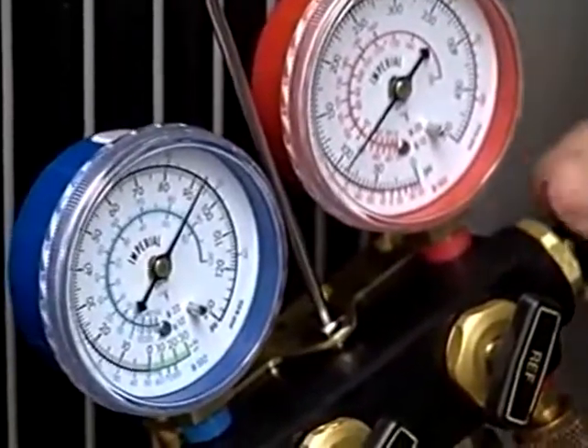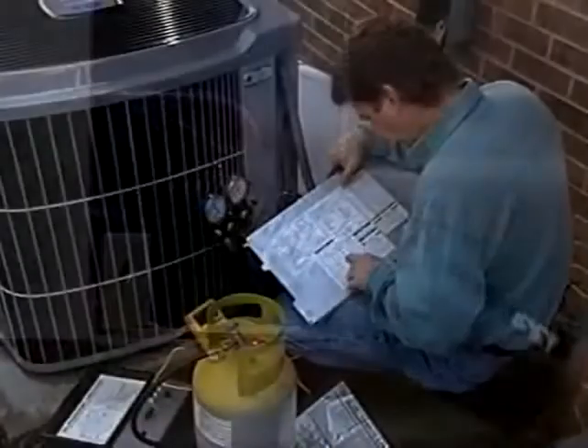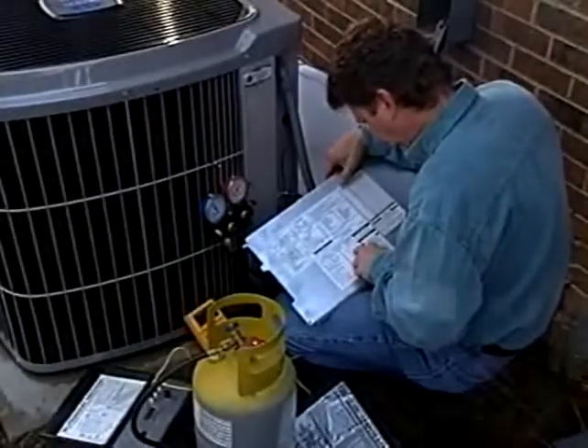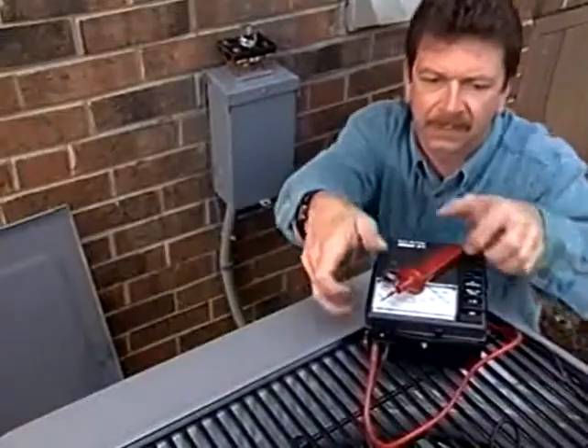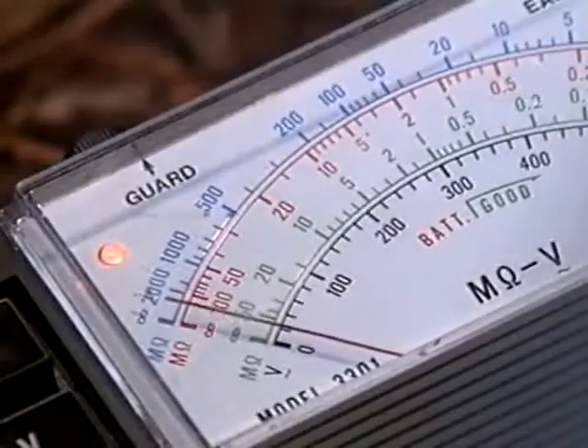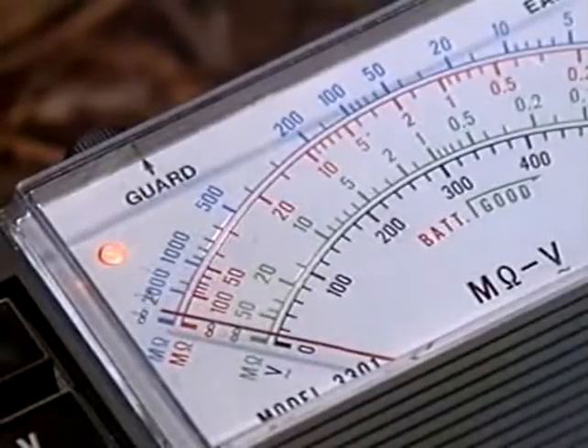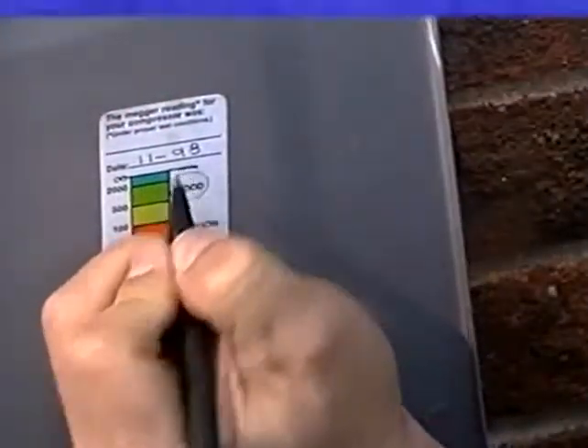Check the pressure gauges and measure your amperage to make sure all the components are working properly. Finally, be sure to get a megger reading. This checks the integrity of the windings of the compressor and can provide important baseline information for future service technicians. Be sure to leave a record of the megger reading in a place that it can be easily noted.